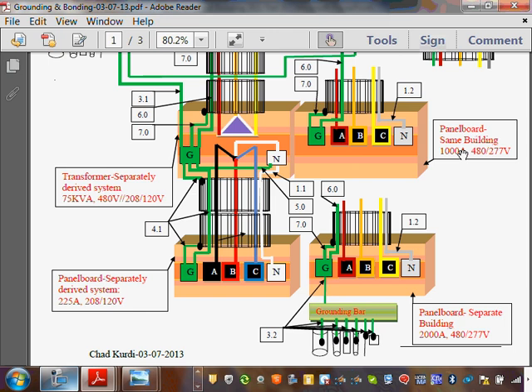I emphasize the word existing, and the neutral will act as an equipment grounding conductor and a grounded conductor. Then you bond the neutral to the ground. Only on existing building. Okay, any comments or questions? Any comments, guys, about these? So that's how we ground and bond at the separate building. Straightforward, no gimmicks. If you have PVC coming in here, no need for this. If you have a cable coming in here, directly buried cable to the second building, no bonding, no number 7.